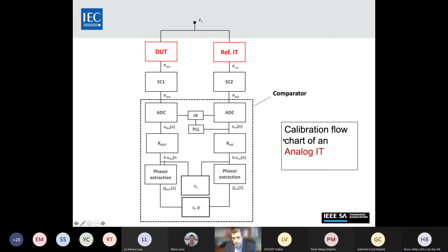What next? What is going to be according to the new generation of instrument transformers, in particular in case of device under test, I mean instrument transformer with digital output, and reference instrument transformers with analog output. In this case, the block diagram, the representation of the setup is made slightly differently than before, because we need to have a PLL for locking the signals. We need a general clock for, let's say, triggering both sides of the setup.